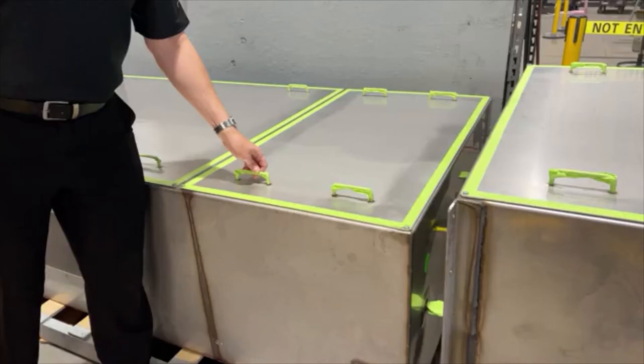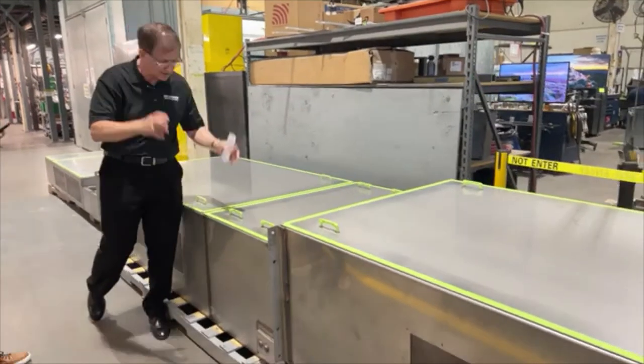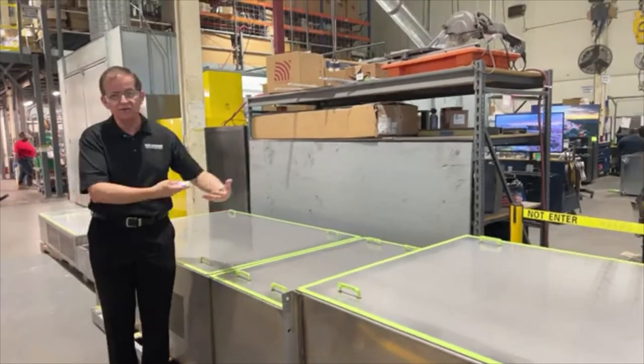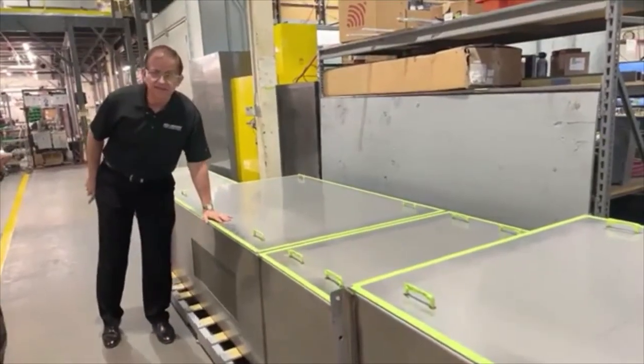This is the clean side and then this is what we call the dirty side. Usually the filters are attached on the outside of the chamber and the power comes through some kind of penetration — a connection that makes an RF seal between the clean side of the filter and the actual chamber, so the power cables can pass through inside. So the power cables come in on this side. It's okay to have this grid on the dirty side.